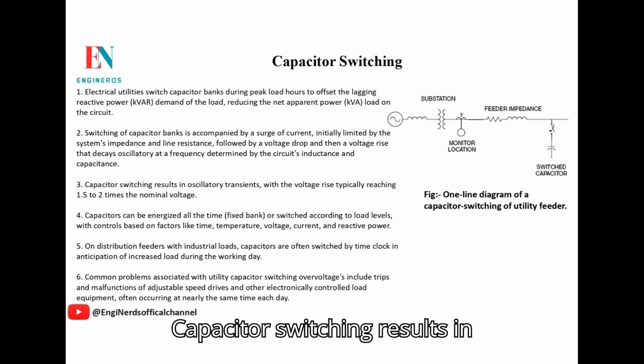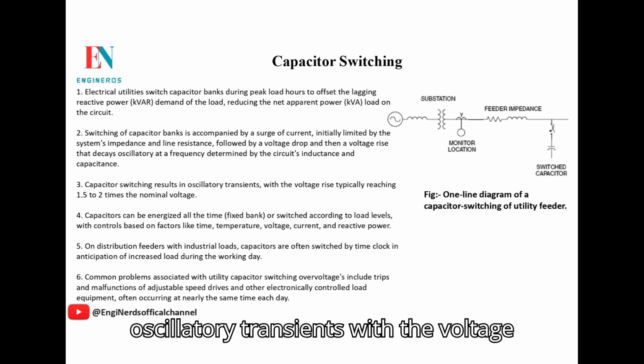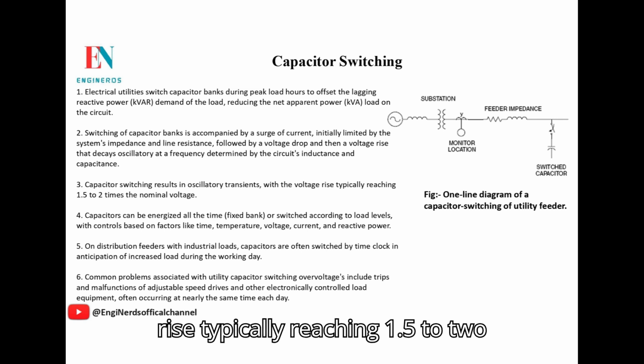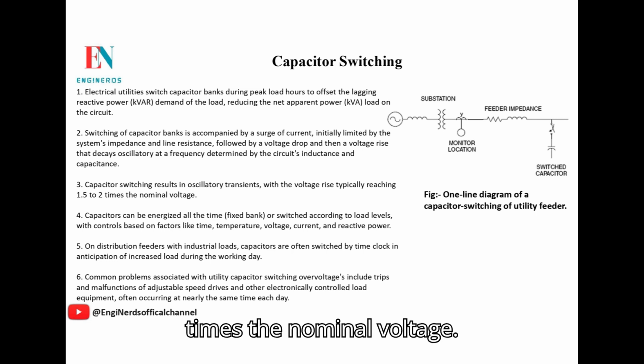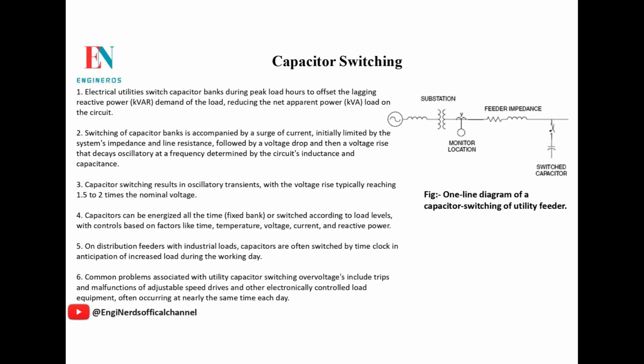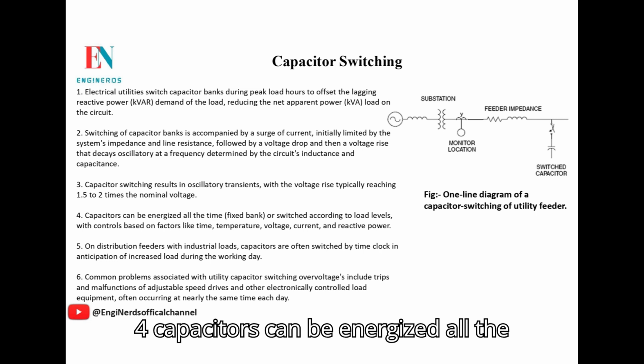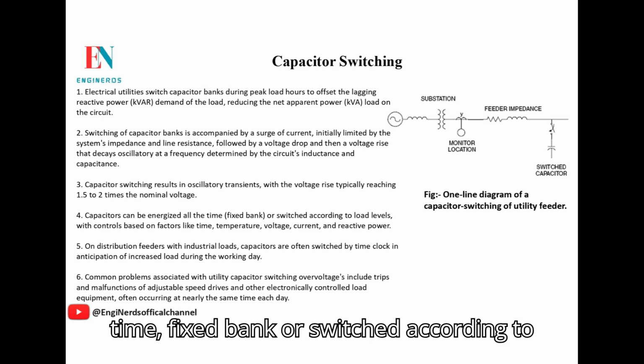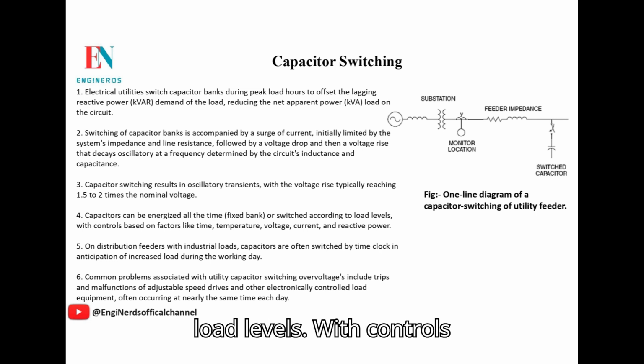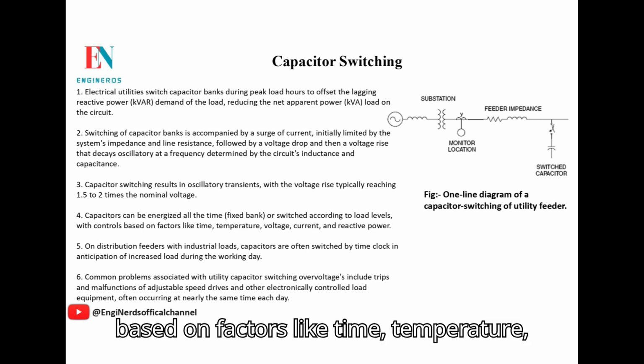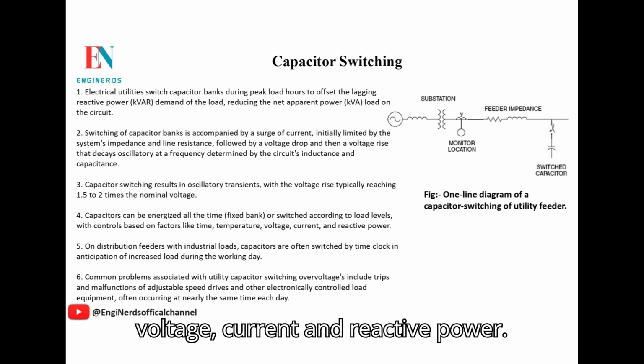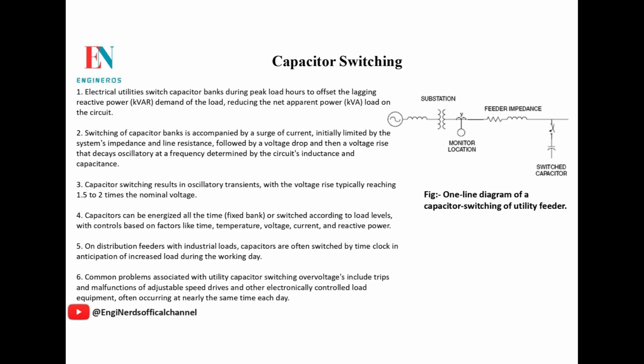3. Capacitor switching results in oscillatory transients, with the voltage rise typically reaching 1.5 to 2 times the nominal voltage. 4. Capacitors can be energized all the time, as a fixed bank, or switched according to load levels, with controls based on factors like time, temperature, voltage, current, and reactive power.